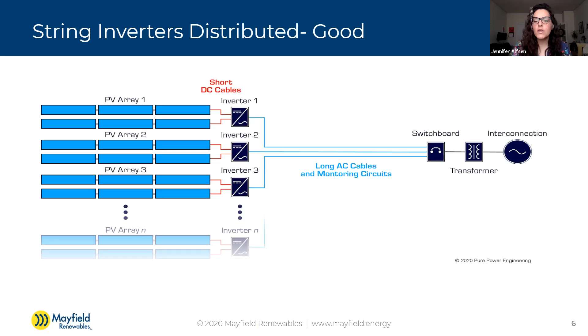Some of the pros: the first one is you can eliminate combiner boxes with this. A lot of string inverters have that combiner box built in. The fused inputs are right there below or on the side of the inverter. You don't need that extra component that you need to purchase, install and wire up. So that's a benefit here. Some string inverters don't have this, and it all depends on how you spec it out. We'll talk about the other type a little bit later.